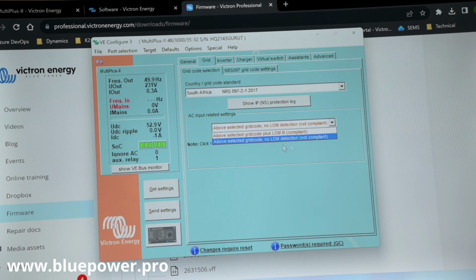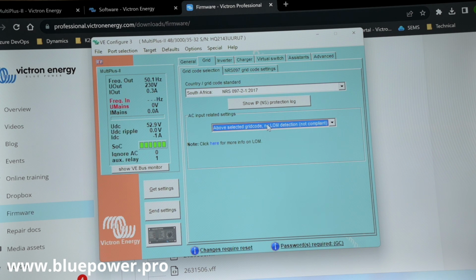So now that our LOM detection has been disabled, we cannot legally connect to an Eskom source on that input. So it's recommended to install a Quattro where you've got a generator on the system, so that you've got a dedicated input for the generator, and you can have dedicated settings for that input. We can disable the LOM detection for our generator input, which is never going to be connecting to the grid, so it is compliant. But our grid connected input has got LOM detection, so it is still compliant as well.